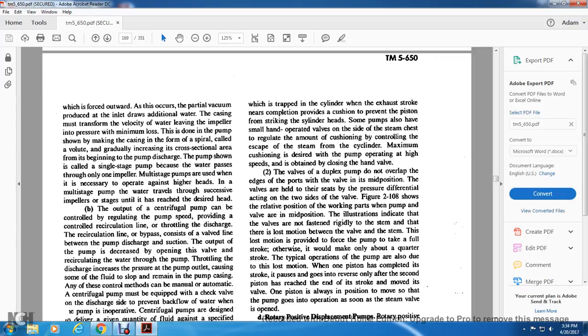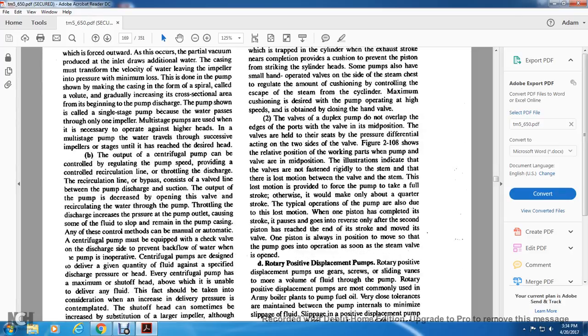The illustration indicates the valve must not be fastened rigidly to the stem. There is lost motion between the valve and the stem. This lost motion permits the pump to take a full stroke. Otherwise, it would make only about a quarter stroke. The typical operation of the pump is also due to this lost motion. When one piston has completed its stroke, it pauses and goes into reverse only after the second piston has reached the end of its stroke and moved its valve. One piston is always positioned to move, so the pump goes into operation as soon as the steam valve is open.